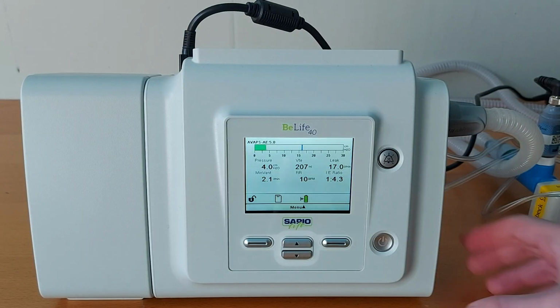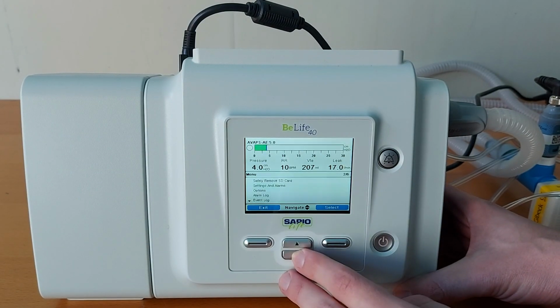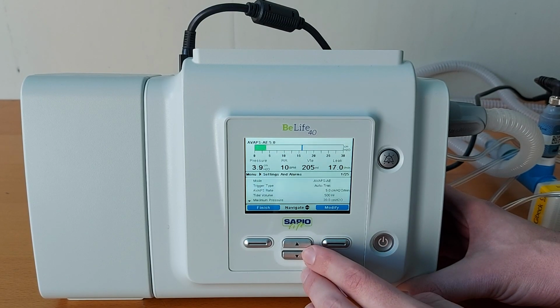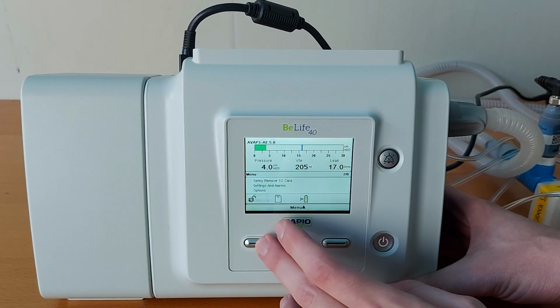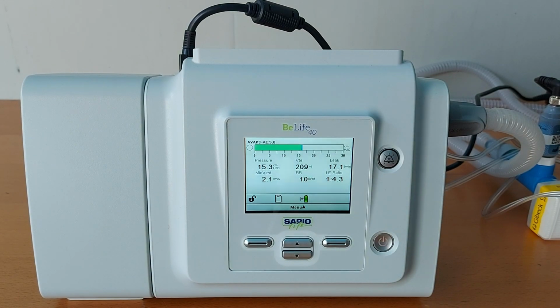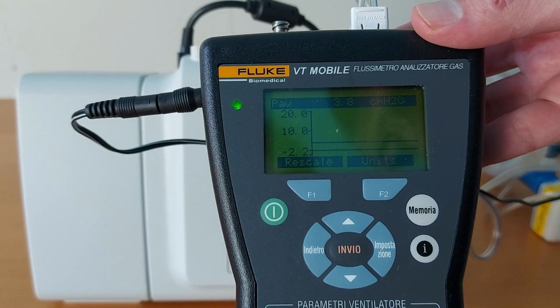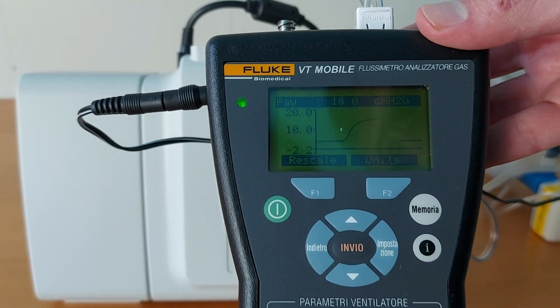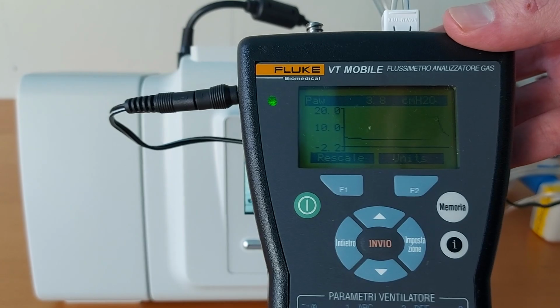Set the unit to operate in BiPAP mode. Verify that the unit maintains the set expiratory pressure level, switches to the set inspiratory pressure level when trigger sensitivity is reached, and switches back to the set expiratory pressure level as described by the operator's manual.